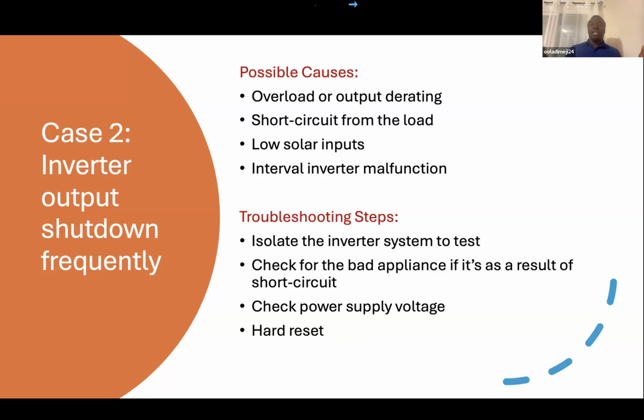So you have to troubleshoot it like I explained. First, isolate the inverter and let it run on battery only. Isolate the input and the output. I presume that you use breakers for your input and output, so you don't have to start from scratch. Isolate the inputs, isolate the outputs, run the system only on battery, and restart the inverter and see if it runs normally and is bringing an output. If you're able to do that, first you know that there is nothing wrong with the inverter and the system. Then you bring in your inputs, you bring in your grid.